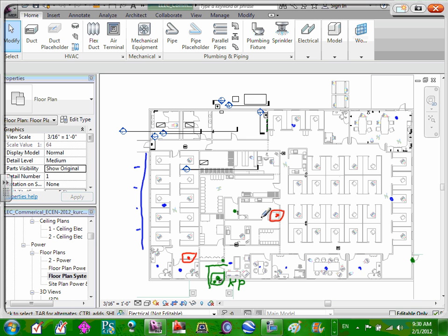Look at what they use for motion detectors, and look at the coverages. I can get one that you can put in the middle of a room, and it can cover all the way around 360 degrees, and it covers 50 feet out. Or I can get one that's meant for a corridor that has a tight beam that shoots down a corridor 100 feet. So there are different coverages that you might want to look at.